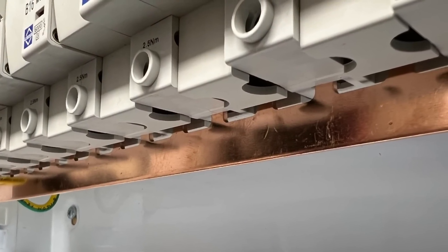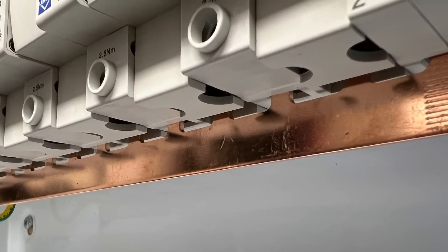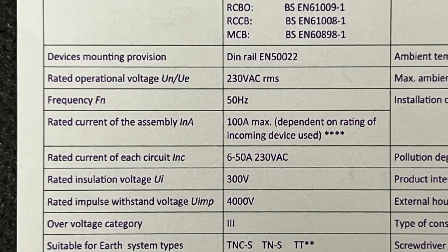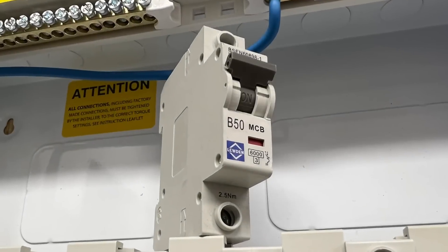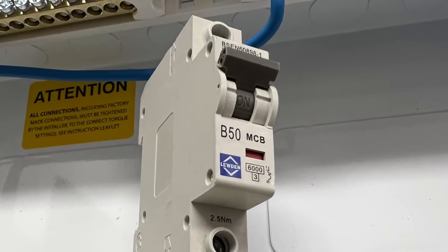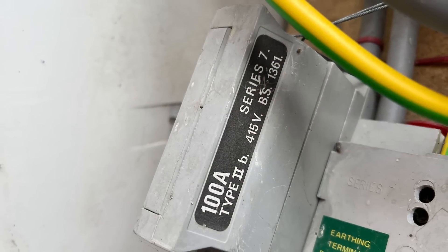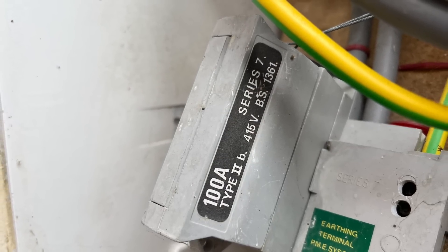It's important to understand that this isn't just about the current carrying capacity of the busbar or the flexible conductors inside — it's about the assembly as a whole. The consumer unit will have been tested to a value of current that it can handle, and it's important not to exceed that value. Then we have IN, which is what we sometimes refer to as the nominal rating of an overcurrent protective device — the number on the front showing how much current can pass through it without tripping. This is the rating of the overcurrent protective device of the incoming supply, which in a domestic installation is likely to be the fuse in the supplier's cutout.